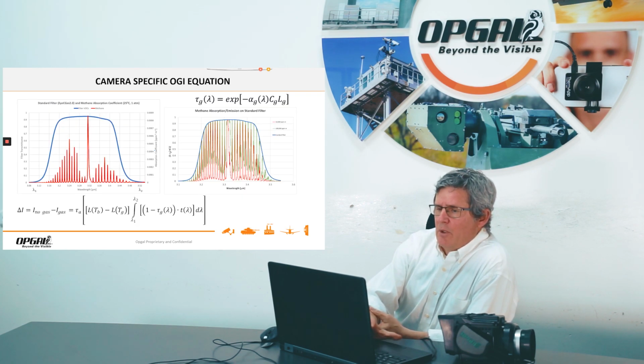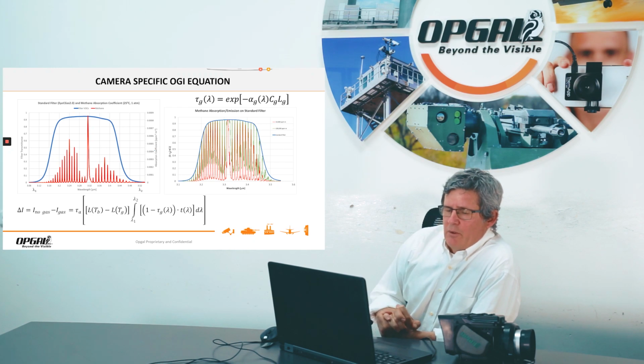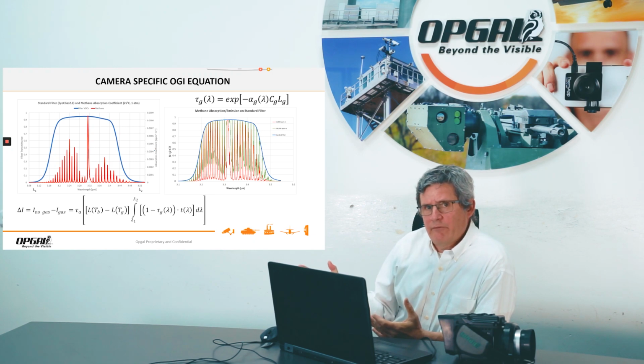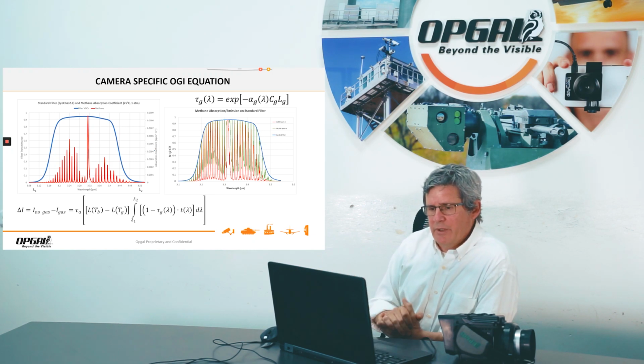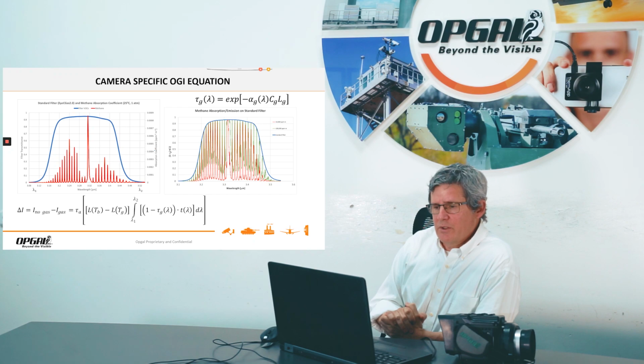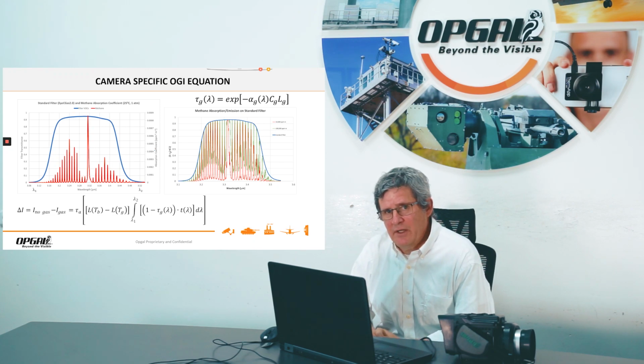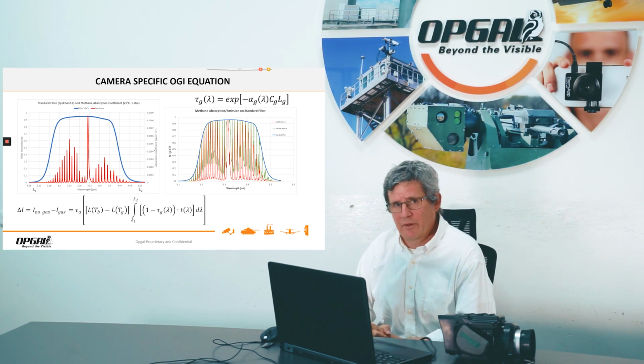So we talked about the radiative transfer model of the atmosphere, but we need to understand that for each target gas, we will put a different type of bandpass filter to actually transmit the radiation where the gas is absorbing the electromagnetic radiation, thermal radiation.